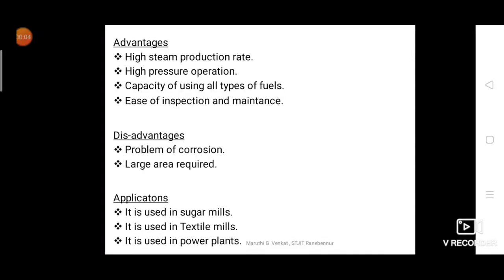The advantages of the Babcock and Wilcox boiler are: first, a high steam production rate of 40,000 kg per hour; second, high pressure operation up to 40 bar; third, it can use all types of fuel to generate hot flue gases; and fourth, inspection and maintenance are very easy compared to the Lancashire boiler.